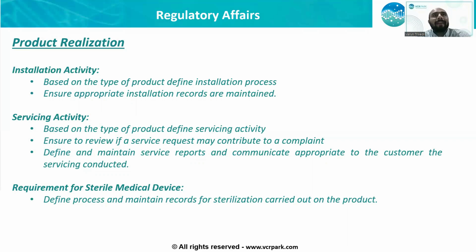Servicing. Again, depending on the product and the kind of servicing elements involved, you need to define your servicing process. You need to ensure that these service requests are properly logged and maintained. Based on the service request, appropriate action shall be taken. Based on the actions that you take, it needs to be recorded and the actions shall be communicated to your customer as well. Let's say the product has been brought back for rework, then as part of your service report, what rework took place shall be documented and a copy of your service report should be shared with your customer.